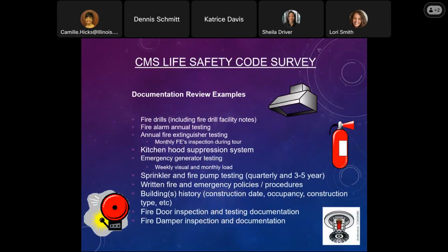Some of the life safety code survey documentation reviews we do include fire drills, kitchen hoods, fire extinguishers, sprinklers, and fire pumps if they have them. We look at emergency policies for fire and evacuations, and building history and date of construction, because that helps determine if it's under existing or new requirements. We do fire door inspections for doors separating stair towers, which have to be done by a third-party testing company. We also do fire damper inspections and documentation reviews. That's just a few of the items we look at during our inspections.